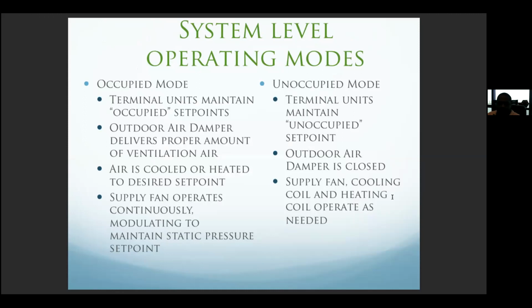So the building is either in occupied mode or unoccupied mode. Occupied mode is when there are people and your building needs to perform accordingly. Unoccupied mode may be an office space that is empty after 5 or 6 p.m. and there's nobody there, so you don't need to maintain the same set points that you would during the day. So the major difference is occupied set points versus unoccupied set points. In the occupied mode, as per building code, we need to deliver a minimum amount of fresh air to the building at any given point in time. In unoccupied mode, that is not necessary, as the building is unoccupied and you can recirculate the air, if it is safe to do so, assuming there's nobody there. The supply fan operates continuously during occupied mode, whereas in unoccupied mode it only works as necessary to maintain unoccupied set points.